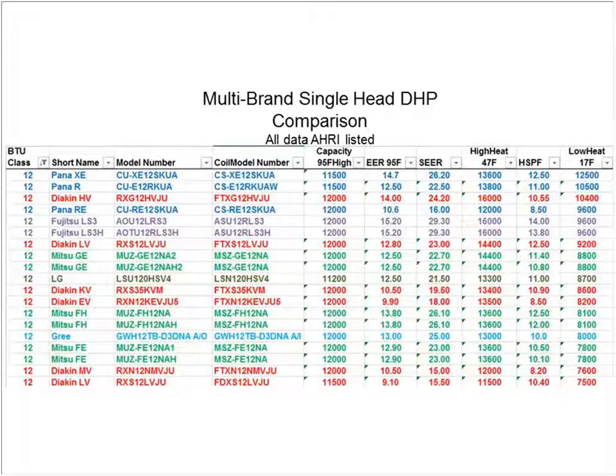However, the criteria is what happens at 17 degrees, because at some point we almost always will see some low temperatures in our world. And we have to be conscious of the builder's pain points. What the builder doesn't want to do is select a product that is going to put him at risk. If he builds 25 houses and all of a sudden it drops down to 20 degrees outside, he's got 20 potential customers calling up saying, hey, your heat pump's not giving me enough heat, my house is freezing.